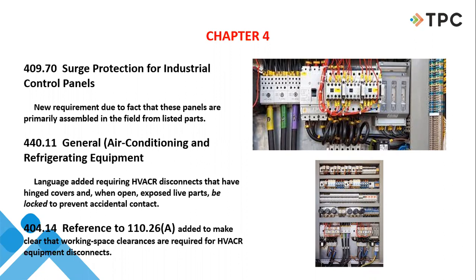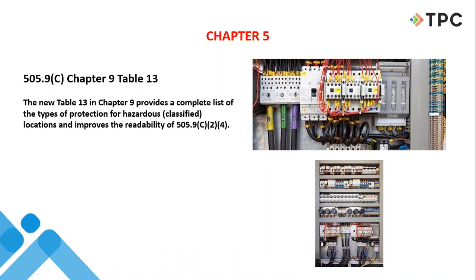404.14 is a reference to 110.26A to make clear that working space clearances are required for heating and air conditioning refrigeration equipment disconnects, the same as they are for other equipment. There's a new Table 13 in Chapter 9 that gives a complete list of the types of protection for hazardous locations. The goal was to improve the readability of 505.9. I've noticed in a lot of different places in this document, they're beginning to favor a list format. And I think it's a dandy idea.